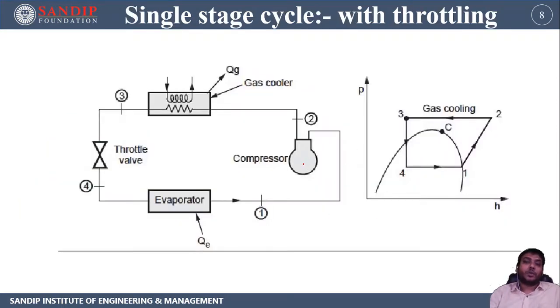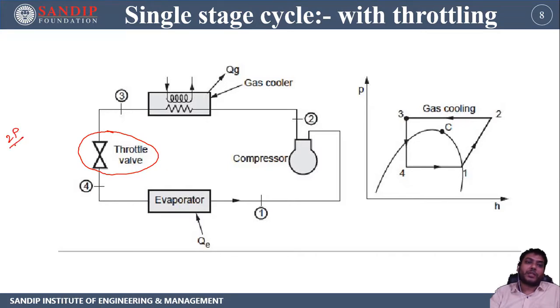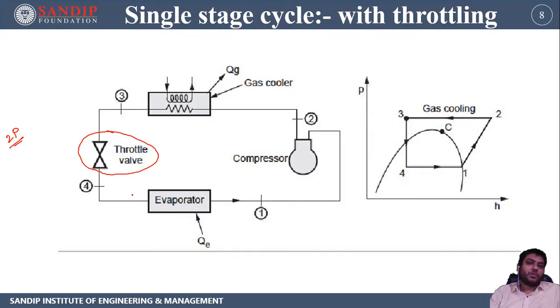Let's start with the single stage cycle with a throttling device. If you are using a throttling valve, this cycle is known as single stage with throttling. Single stage means there is one single cycle — if only two pressures are available, one higher and one lower pressure, we say it is a single stage cycle. The components are: a compressor, a gas cooler, a throttle valve, and an evaporator. This is the pH diagram for this particular cycle.